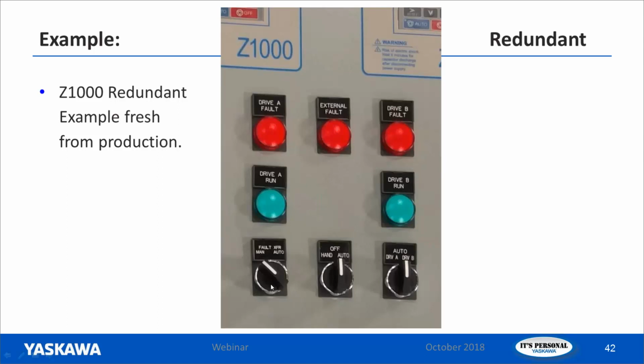So right here, the fault transfer switch is where we can tell the package how we want it to react on a drive fault. If we have it over here in the manual position, then the drive will be faulted and it'll be waiting for you to tell it to run the other drive. Or we can have it in auto. That way, if the drive is running and it does fault, it'll automatically switch over to the other drive.